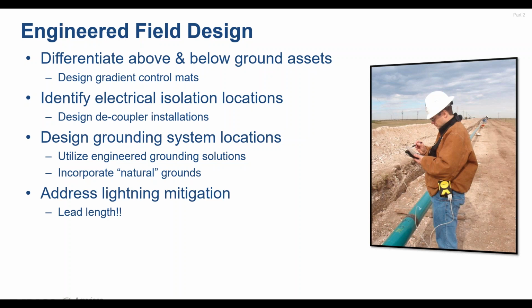We have to think through lightning and how that event affects both the HVAC system and then the subsequent impact on our pipeline system. Lightning is a different fault condition than an AC 60 hertz event, because you see, lightning does not only present as a 60 hertz event. It has extremely fast rise times. It has a slow decay time, or a slower decay time, and it's not a defined frequency. Most often it will have components of very high frequency as a part of that.